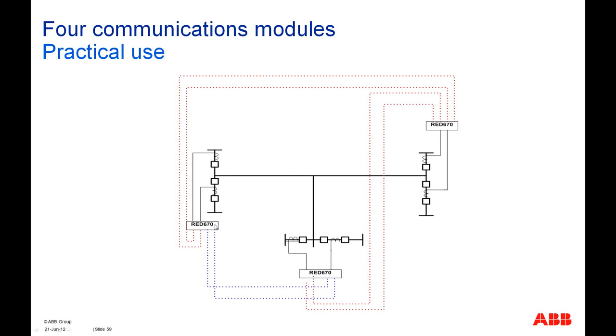In the 3 terminal lines right now, you can see that this topology for the communication can be used. And in this particular example, we will have 4 communication modules. We call it LDCM, line data communication modules. And now you can see by using these 4 communication modules, all the relays are actually talking to each of the other 2 relays. So, for example, this local relay is talking to this relay as well as to this relay. And similarly, this particular relay is talking to this relay as well as to this relay. So this is a very nice redundant communication network which you can create by using these communication modules. If one of the links breaks, for example, then it will automatically reroute the communication.